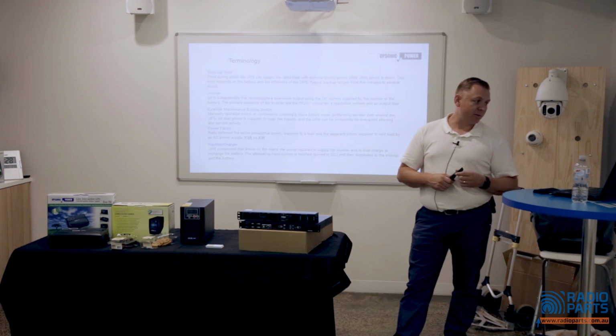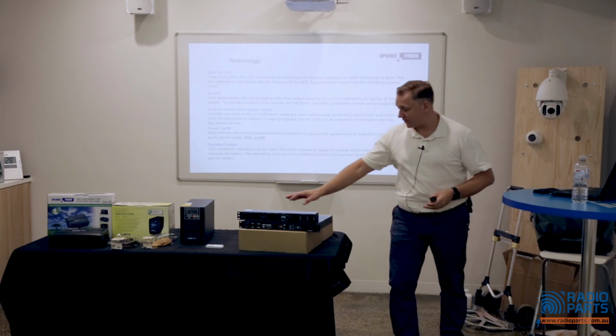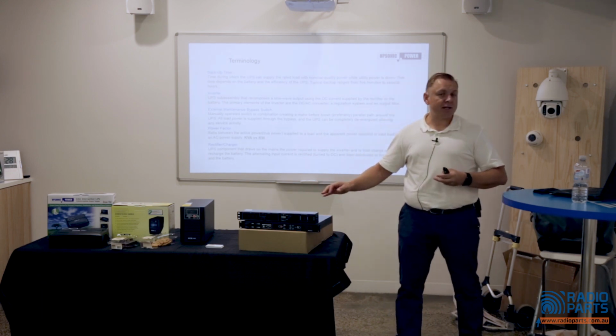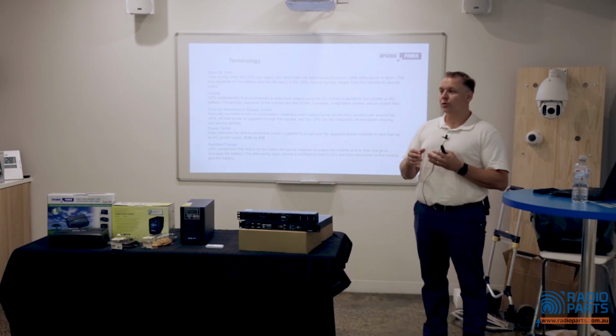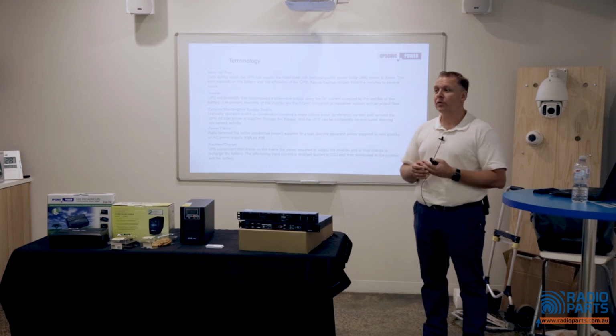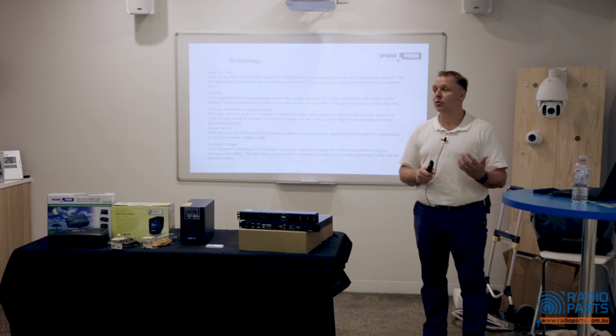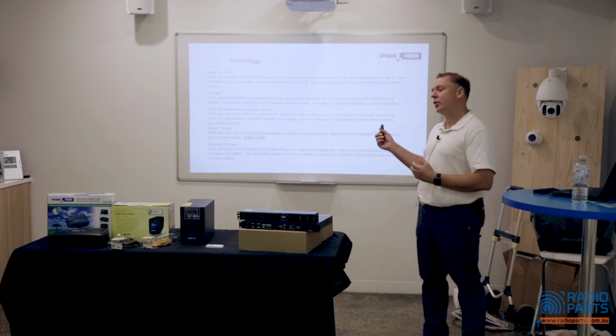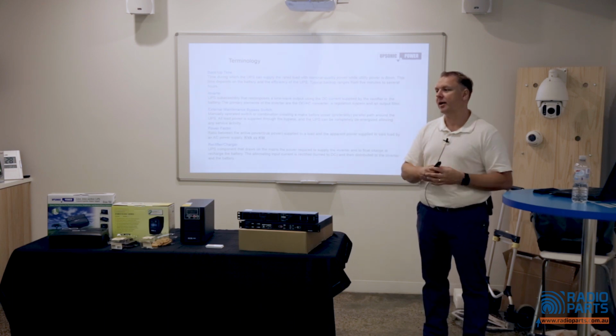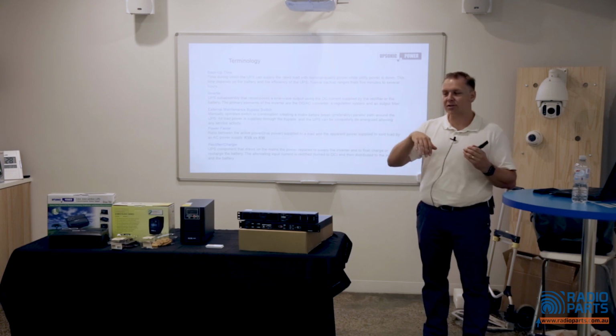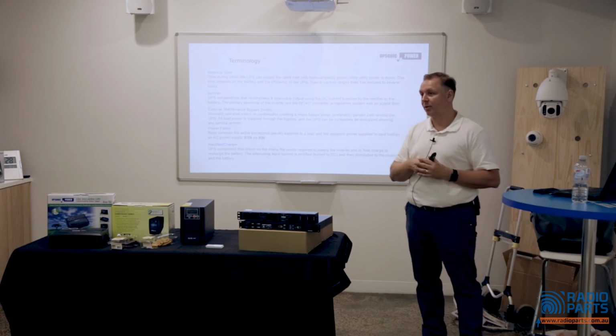Also have the external maintenance bypass switch - a manually operated switch, like the example here, that allows us to do maintenance or work or even complete removal of the UPS while maintaining supply to the load. So sometimes also called a wraparound switch. When we get to one of the diagrams later on, you'll see why that terminology comes up, because the supply sort of wraps around the UPS as opposed to running through it.